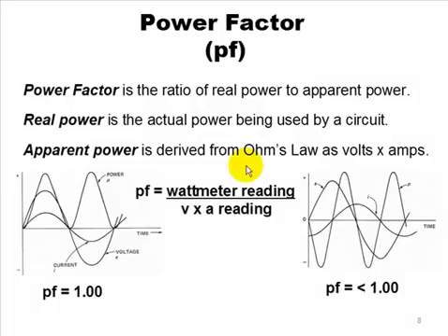Read the amperage there while the unit's running, obviously. And multiply voltage times amperage and divide that into the watt reading. And that will tell you how efficient that circuit is. Because this is the standard efficiency formula. If you want to know how efficient something is, divide the output by the input. Take a gas furnace. If it's 80,000 BTU output and 100,000 input, you divide the output by the input, you're going to get the percentage of efficiency. If you divide 80,000 by 100,000, you're going to get 0.8, or 80% efficient. And that's what we're doing here. We're saying this is the actual wattage we get from a watt meter reading. And this is the voltage I read times the amperage I read, which essentially is Ohm's law. And I divide this into that. This is my input. That is my output. That's what power factor is.